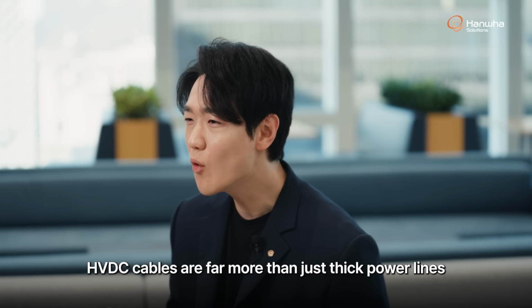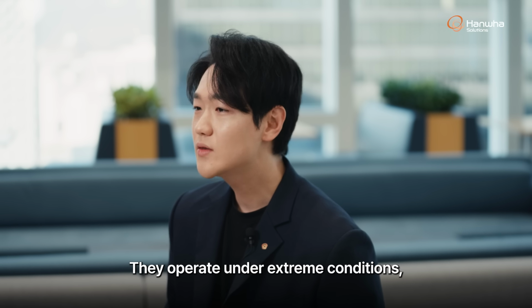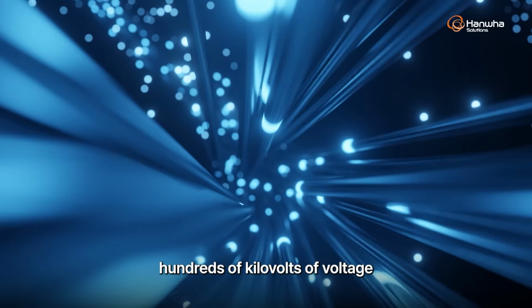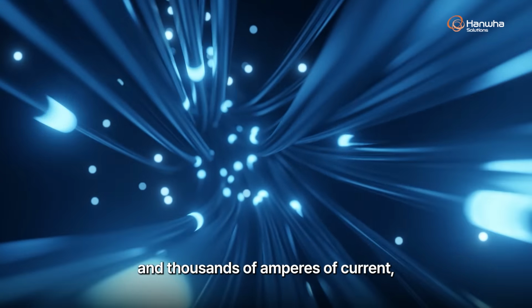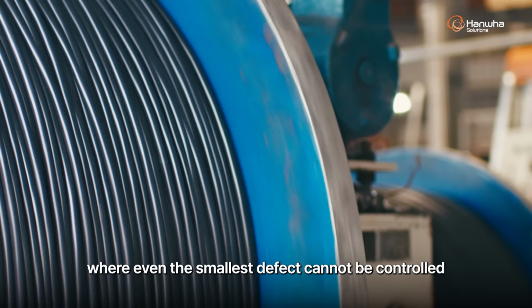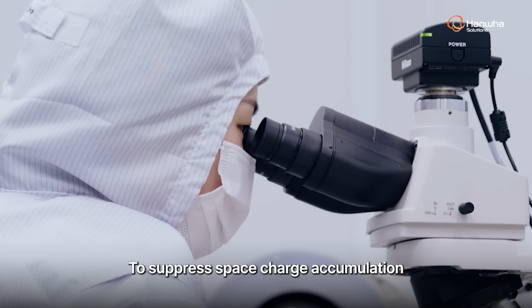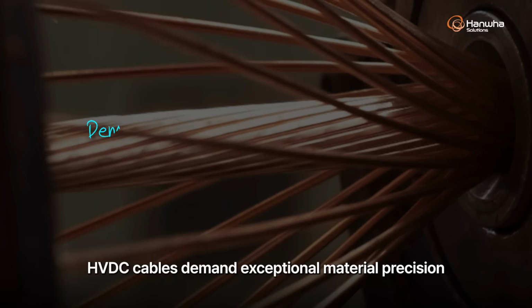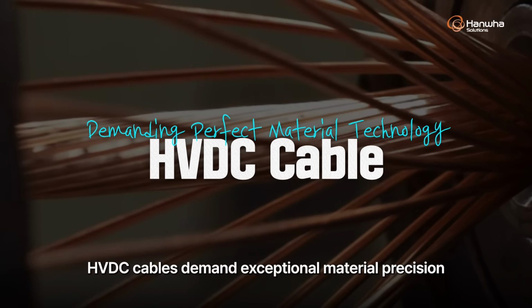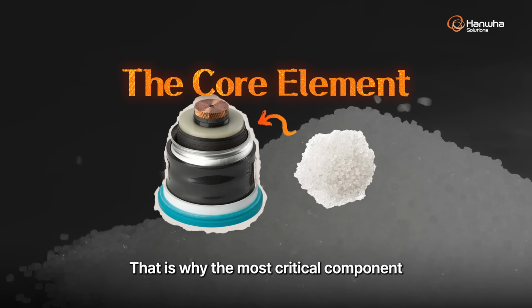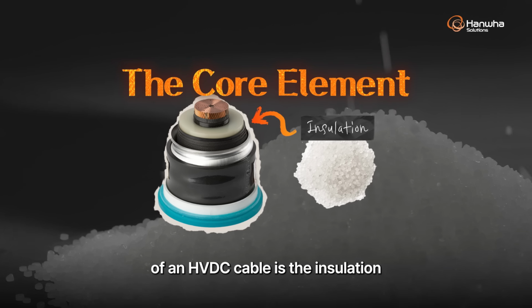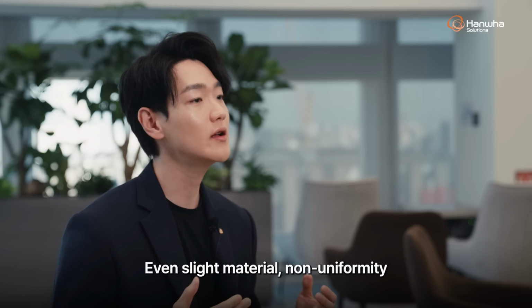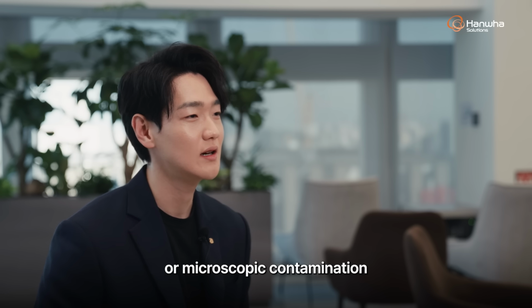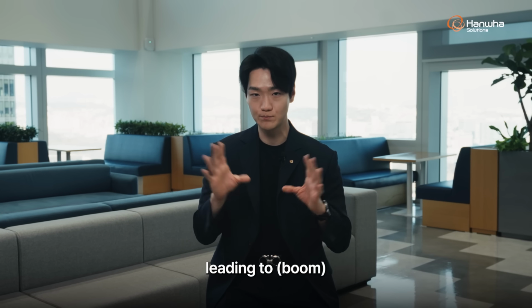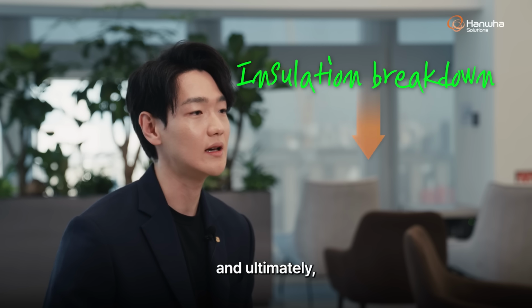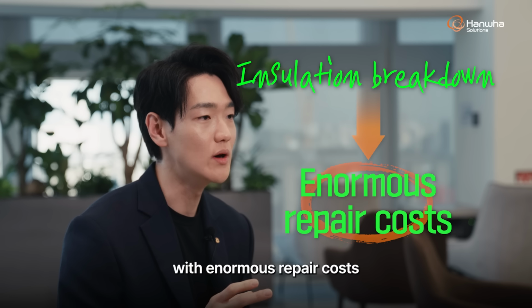HVDC cables are far more than just thick power lines. They operate under extreme conditions, hundreds of kilovolts of voltage and thousands of amperes of current, where even the smallest defect cannot be tolerated. To suppress space charge accumulation and maintain electrical insulation, HVDC cables demand exceptional material precision. That is why the most critical component of an HVDC cable is the insulation. Even slight material non-uniformity or microscopic contamination can concentrate electrical fields, leading to insulation breakdowns, and ultimately catastrophic system failure with enormous repair costs.